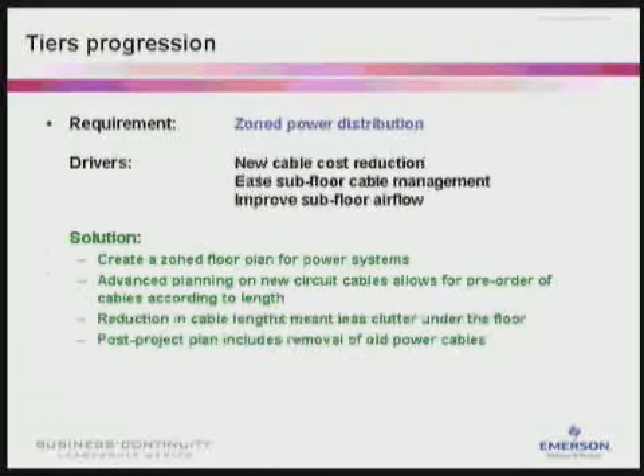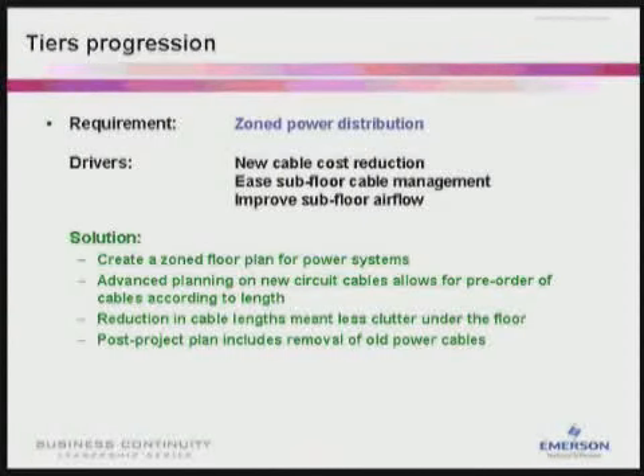Zone power distribution was employed to improve subfloor cable management as well as improve subfloor airflow. A zoned floor plan was created for the power system. Advanced planning allowed new circuit cables to be pre-ordered according to length. A reduction in cable lengths meant less clutter underneath the floor, and the post-project plan included removal of old power cables to help improve subfloor airflow.